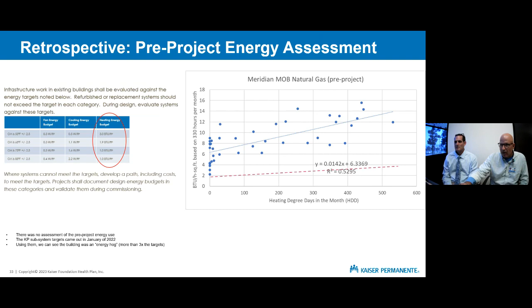So we do have energy benchmarks now, and the building was well over those, at about 6.3 BTUs per square foot. But the design team really didn't have any access to that data. That's important, because had they had access to it, they could have done something about it, possibly going out to the zones, since we could have been over-pumping or overheating systems.